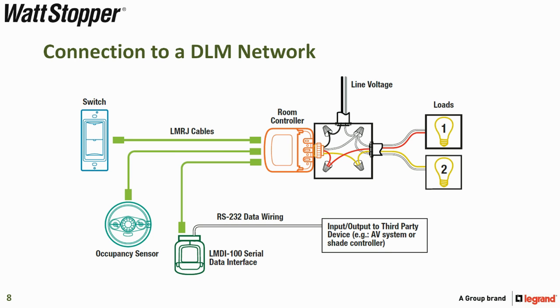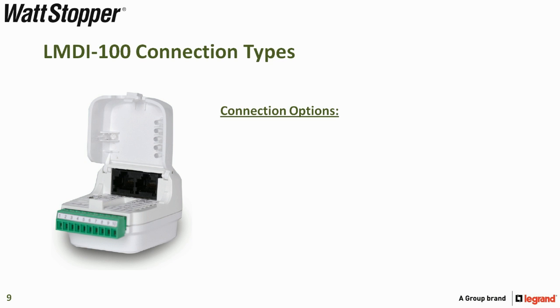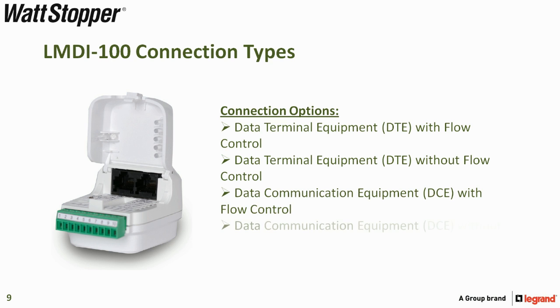The LMDI100 is connected to the DLM local network just as any other DLM device. It is connected using the in-room bus CAT5 and is tied to the third-party system via RS-232 data wiring. There are several different LMDI100 connection types available, including data terminal equipment DTE with flow control, DTE without flow control, data communication equipment DCE with flow control, and DCE without flow control.